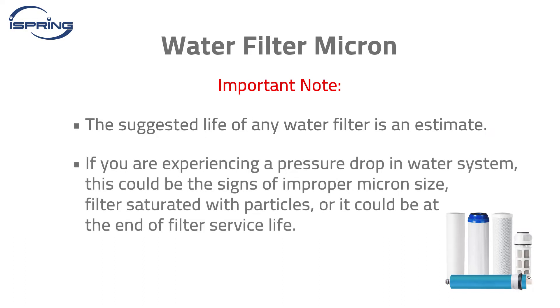If you are experiencing a pressure drop in your water system, this could be the signs of improper micron size, filters saturated with particles, or it could be at the end of filter service life.